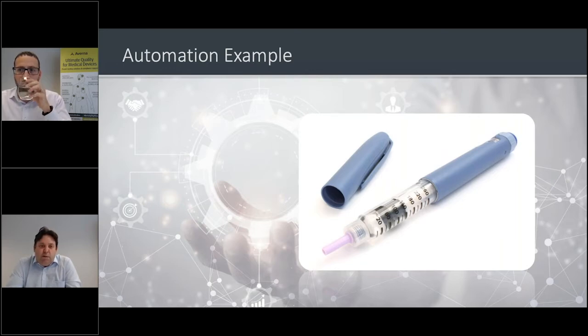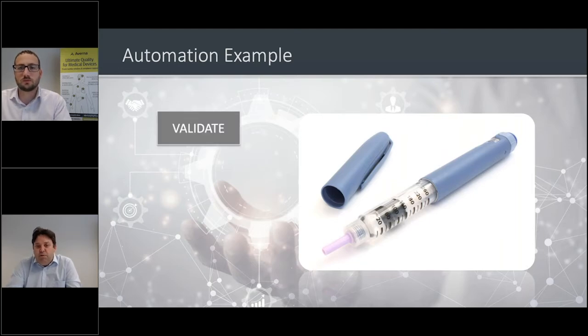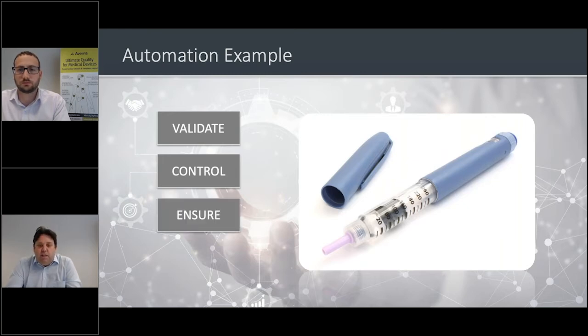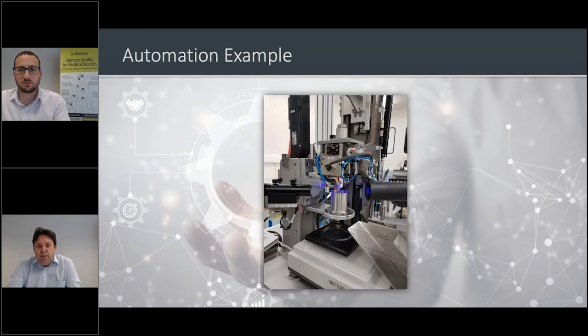This could only be done by performing a destructive sample test that was able to validate if the syringe cap can be removed simply for patients with limited use of joints. They also wanted to control the syringe and measure the needle depth to ensure that the needle was inserted into the right tissue layer. They also wanted to ensure that all the medicine had been ejected from the insert, and finally to monitor the dosing time, as the application of the medicine can be painful for the patient if it's applied too quickly. Based on all these requirements, we designed an automated test system to simulate the reusable applicator in a hands-free, clean environment.